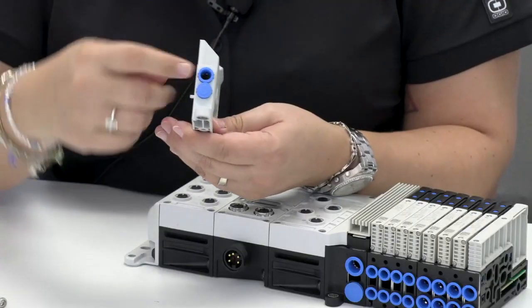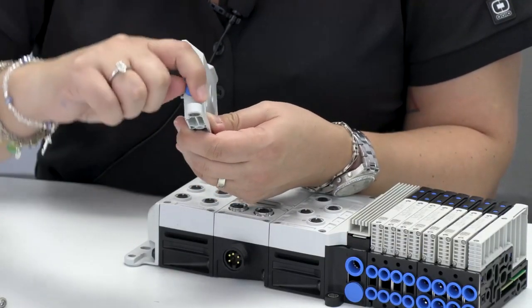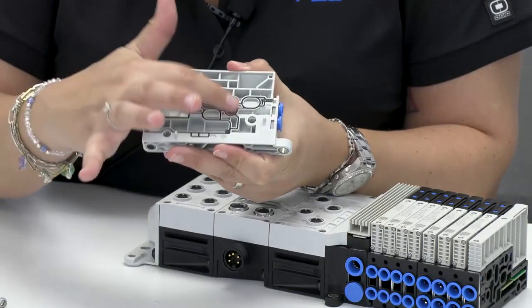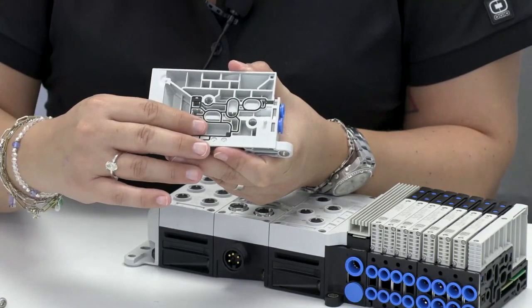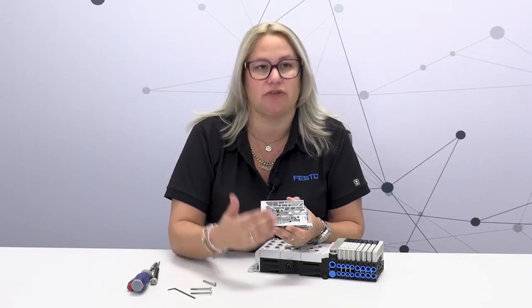In this case, what we're going to have to do is for the end plate we would have to remove this plug and change it for a fitting. Then in here we will put a plug right here that will allow you to then change your pilot from internally piloted to externally piloted.